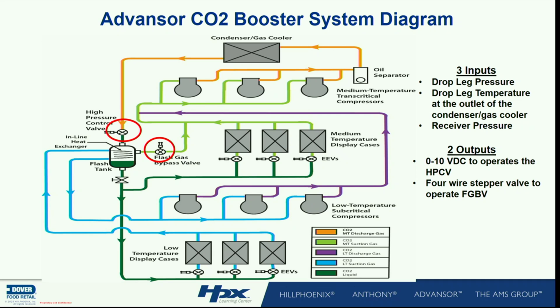And he simply opens and closes based on that pressure and the load coming into it. How much load do I have coming through here? How high of pressure is it? How far is he open, yes? Mode 1, he's probably, depends on where in mode 1 I'm at, 30, 40, 50% open. Are we good? Wherever it's necessary to get to. Those of you who are using a 326A, go to little U24, and that's where your set point will be, or where your pressure is. Or excuse me, how far open the valve is.